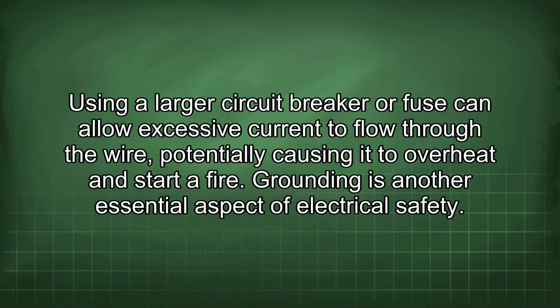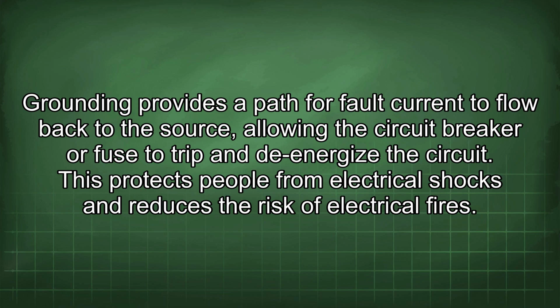Grounding is another essential aspect of electrical safety. Grounding provides a path for fault current to flow back to the source, allowing the circuit breaker or fuse to trip and de-energize the circuit.